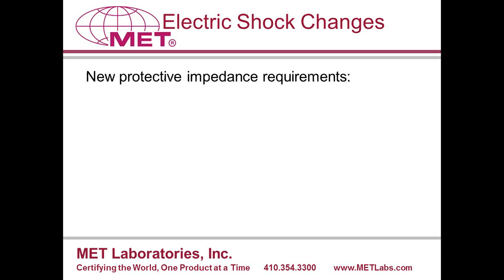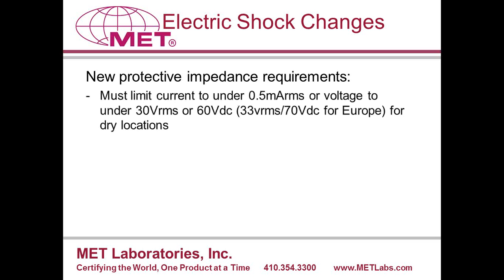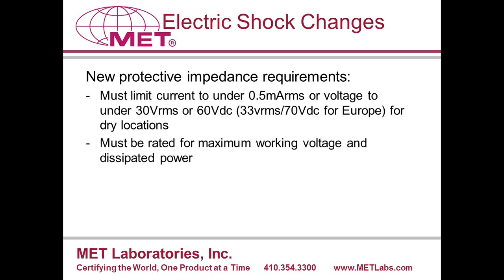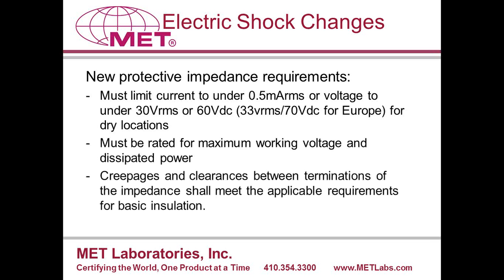If you use resistors in series or any other type of protective impedance as your means of protecting accessible parts from shock hazards, there are new design and component selection criteria which are pretty much the same as those for a single current or voltage limiting device that I mentioned in the previous slide. First, the final voltage or current must be at or below the electric shock safety limits for voltage or current for accessible parts. Next, the ratings of each component must be sufficient for the voltage and power. Last, the spacings on the board for each component must meet creepage and clearance requirements for basic insulation, or reinforced insulation if a single component is used.